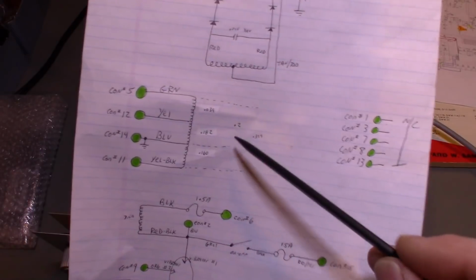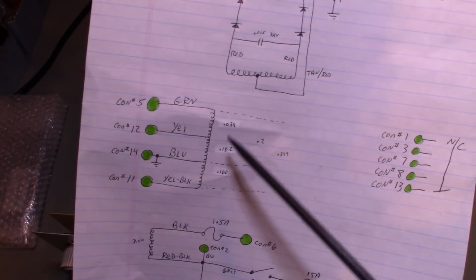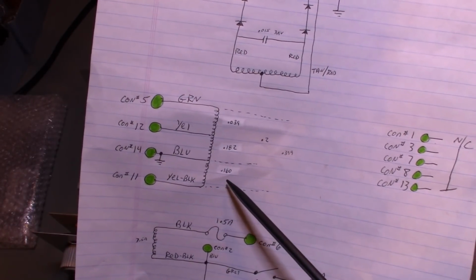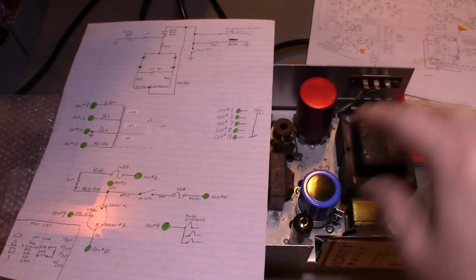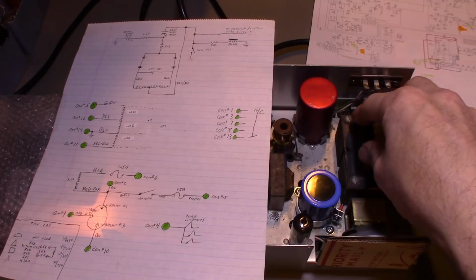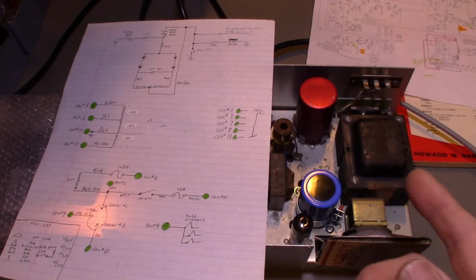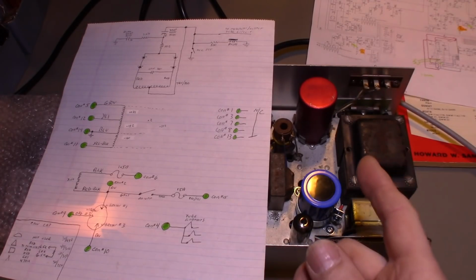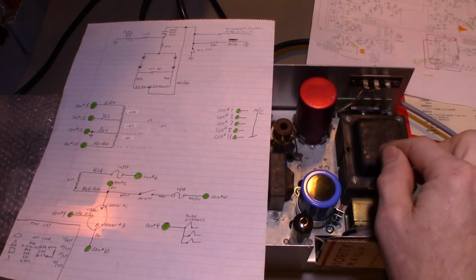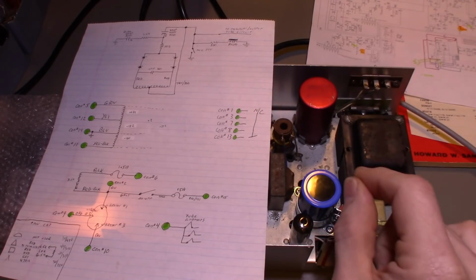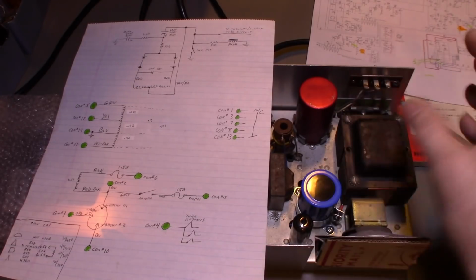Even if you look at this, this is the original paper I did it on, you can see I've got some numbers here. Those are actually resistance measurements I was taking. So the first thing you do if you're trying to figure out wiring for a transformer is, with an ohm meter or just a continuity tester, go through and find which wires that go into the transformer have continuity with any other wire, and then group them together.